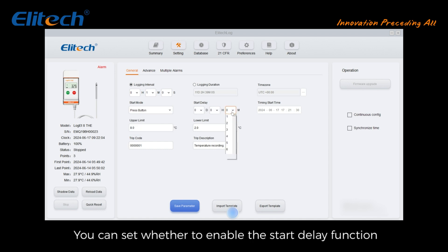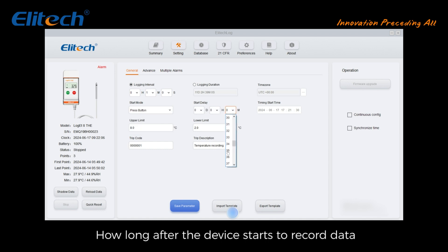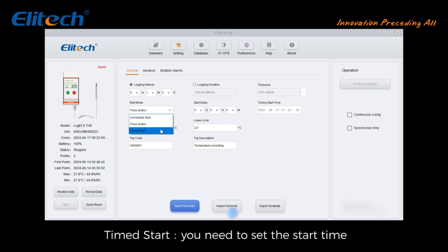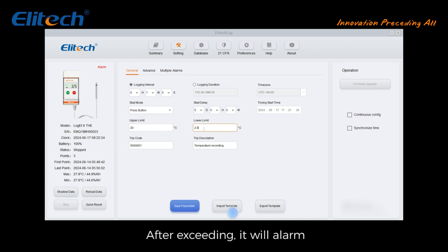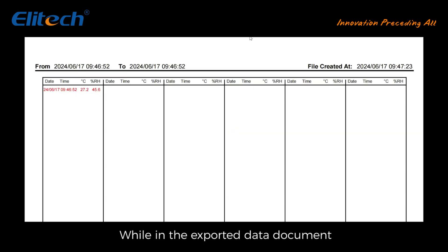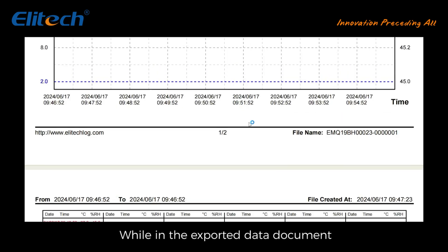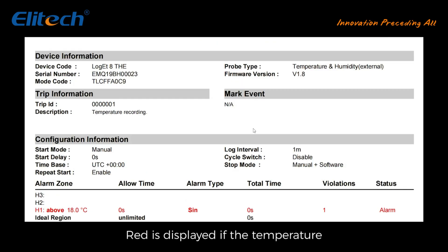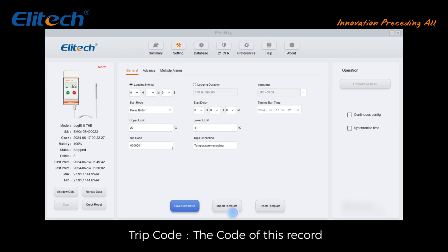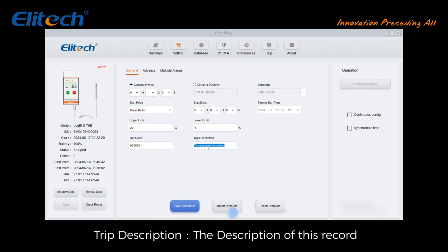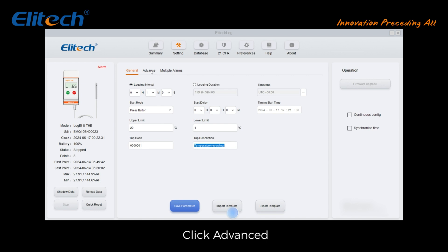Press button mode: set whether to enable the start delay function — how long after the device starts to record data. Time start: set the required start time. Set high and low temperature limits; after exceeding them an alarm will trigger. In the exported data document, red is displayed if the temperature is high, or blue if the temperature is low. Trip code is the code of this record; trip description is the description of this record.